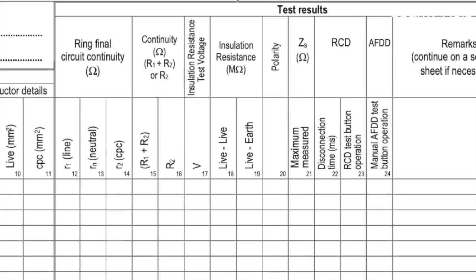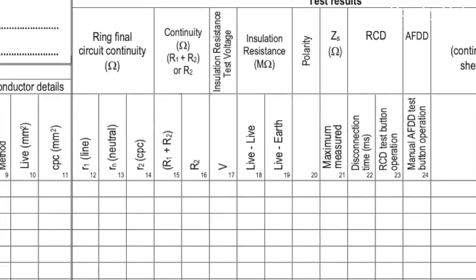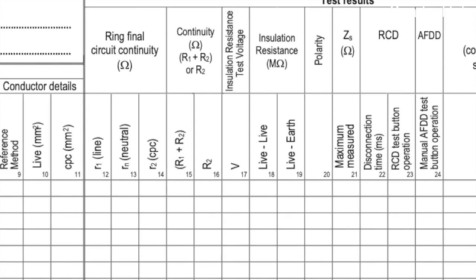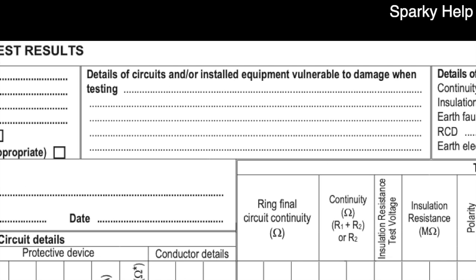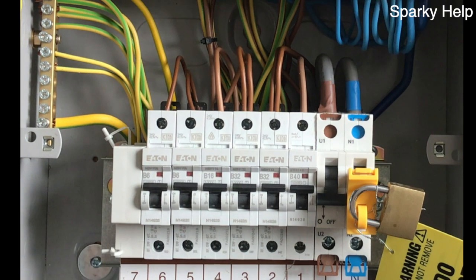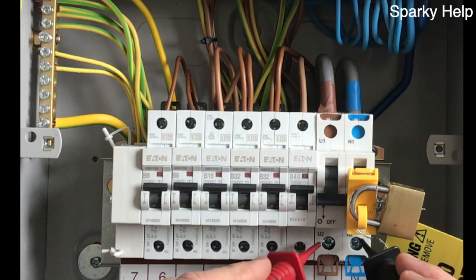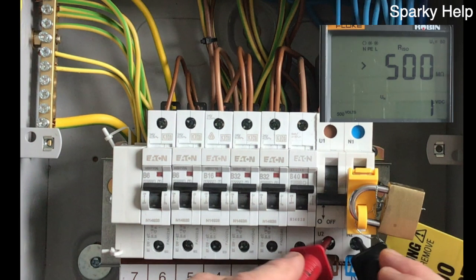When it comes to the test sheet, we have two columns in particular, between live conductors and live conductors and earth, but we have a new one, insulation resistance test voltage, that allows us to record the test voltage for each circuit that we have been testing. But at the top of the form, as always, we have details of circuits and or installed equipment vulnerable to damage when testing. This should record information for all the equipment that you're about to remove. Remember, think of future testers, or the future tester could be you. You'd be glad if people wrote it down. So here we're going to do an insulation resistance between line and neutral, 500 volts, and press the test button.